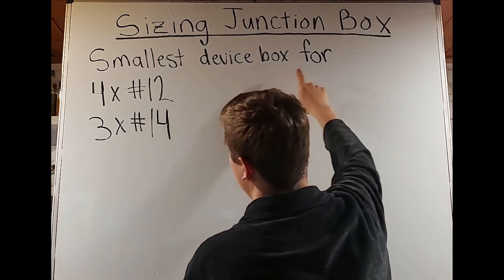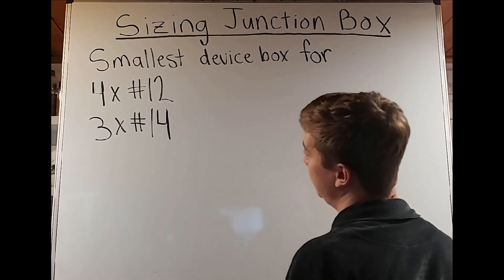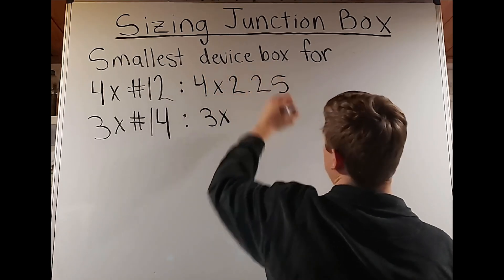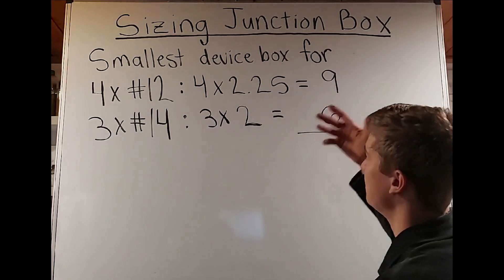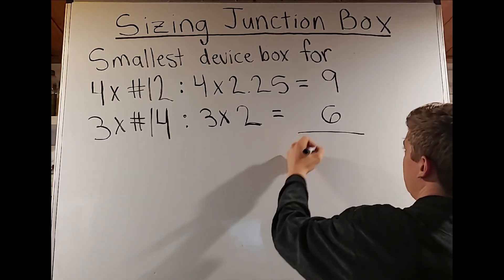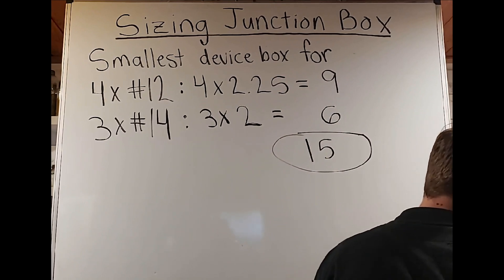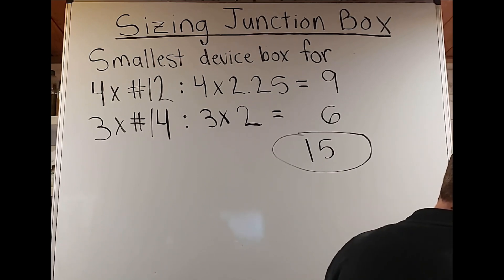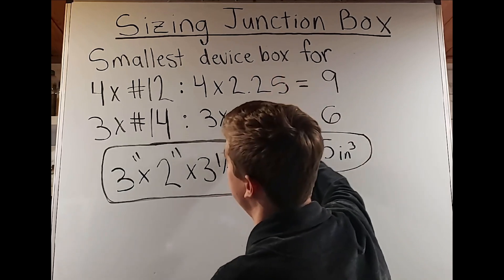Next: what is the smallest device box for four number-12 and three number-14 gauge conductors? First, we calculate the total cubic inches: four times 2.25 equals 9, three times 2 equals 6, total is 15 cubic inches. Now in Table 314.16A under device box, starting from the top and looking for anything 15 cubic inches or above — we find 18 cubic inches for a three by two by three-and-a-half inch box. That is the smallest device box that can fit these conductors.